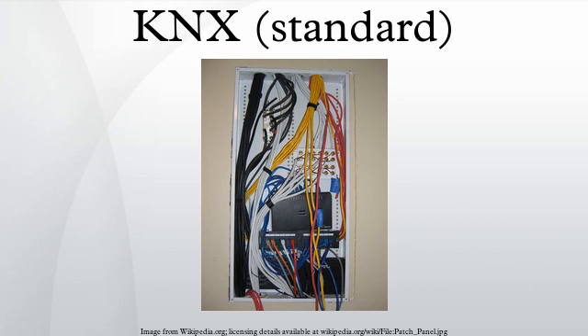KNX allows different bus topologies: tree, line and star topologies. These topologies can be mixed as needed. However, ring topologies are not allowed. The tree topology has advantages over other topologies in cases where a large network has to be created.